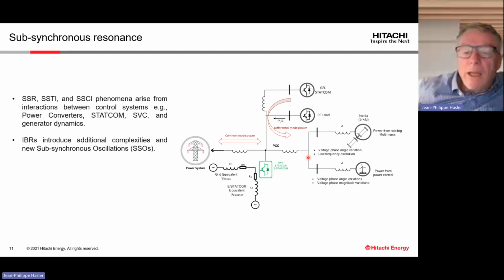And our task mainly is first to maintain, for example, the bus voltage at a certain point. We have to damp harmonics or impedance resonance resulting from the long cable and capacitance you have in the grid. And also very important, we have to minimize the interaction you will have between different devices, because we know nowadays that we have a lot of interaction, for example, between wind farms and maybe STATCOM. That is what we call differential mode. We also have to damp, say, the complete power mode or oscillation you have between the complete plant and the big grid.